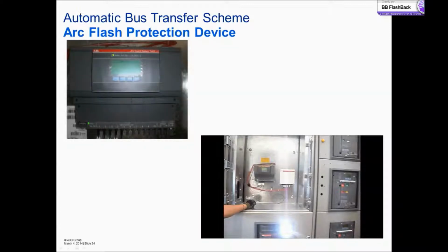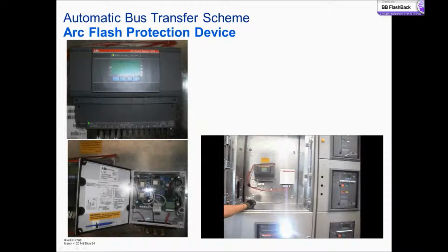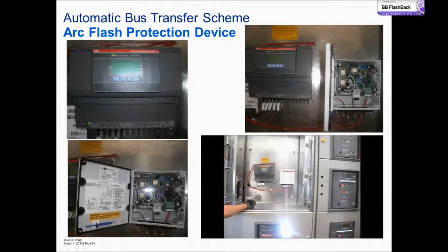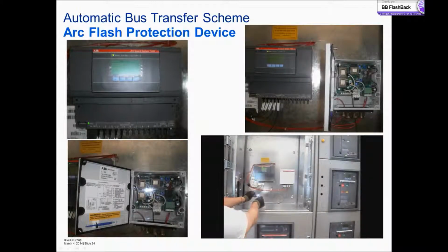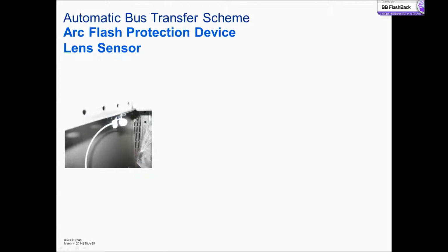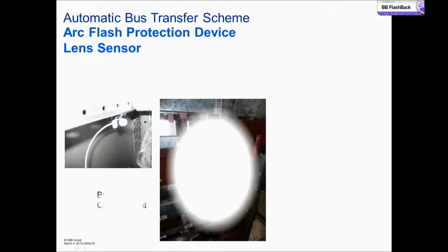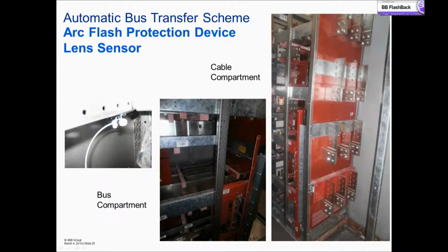The TVOC2 has light detection and current confirmation with the current sensor unit in the case of the arc flash. This is the arc protection relay with the test light. The installation is at the medium height of each section of switchgear, one in the bus and one more in the cable compartment, when we have barriers between cable compartments or it is an arc resistant switchgear.